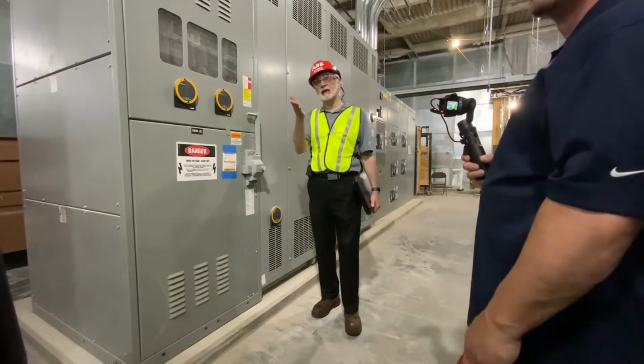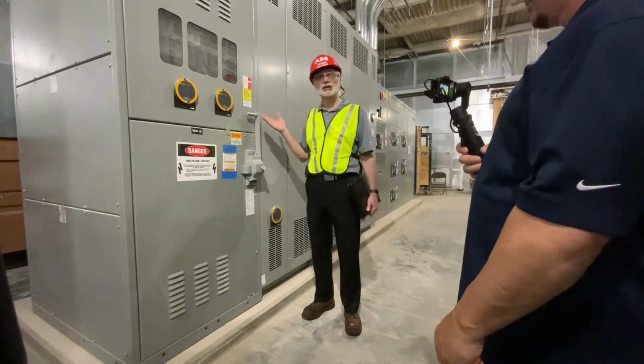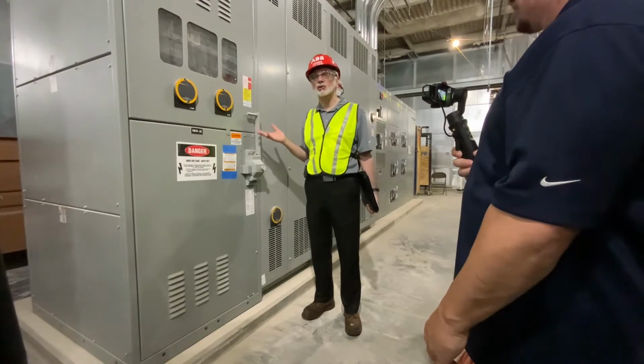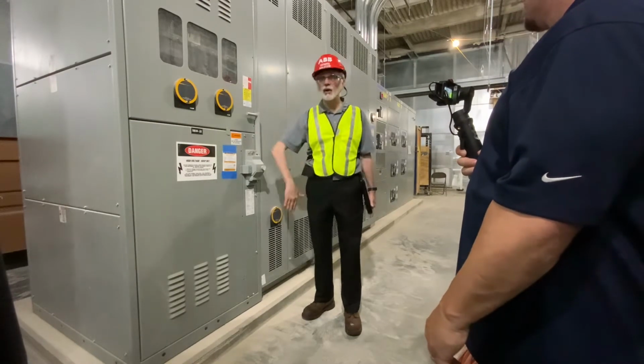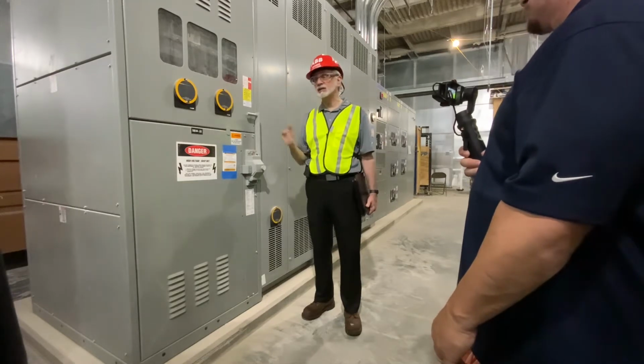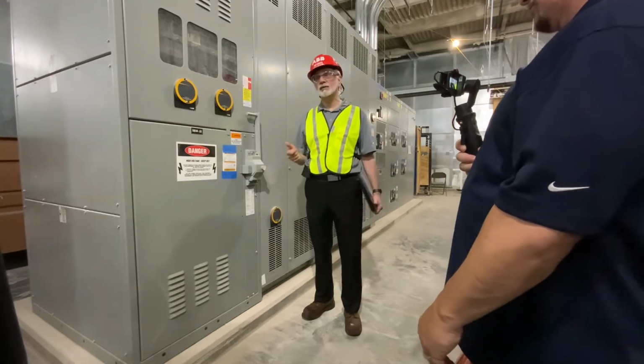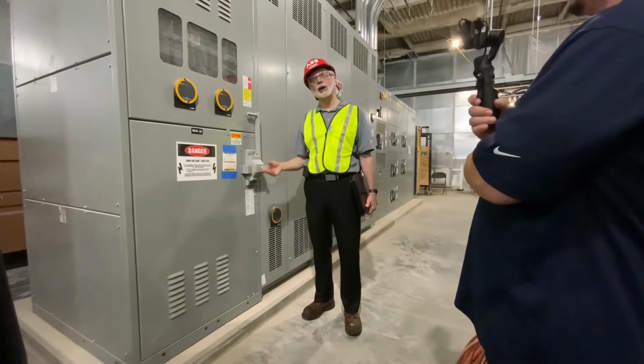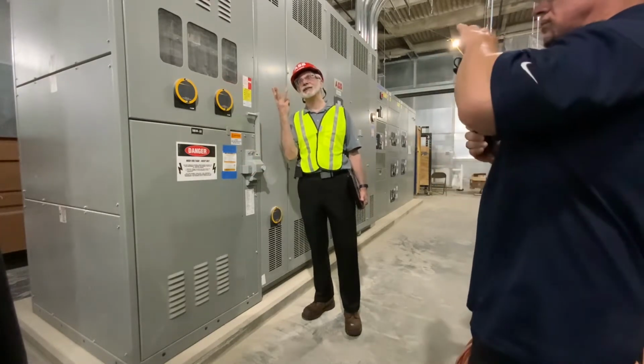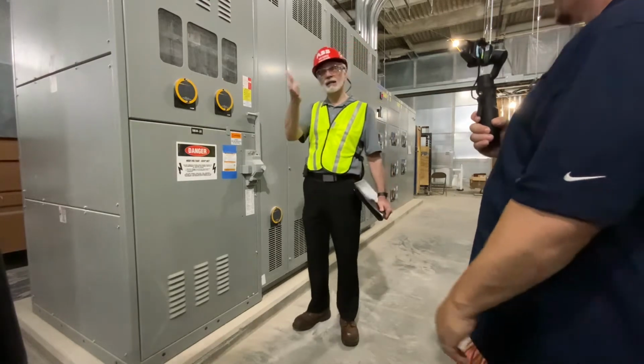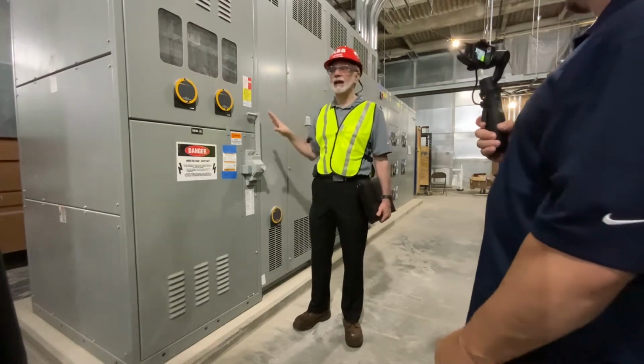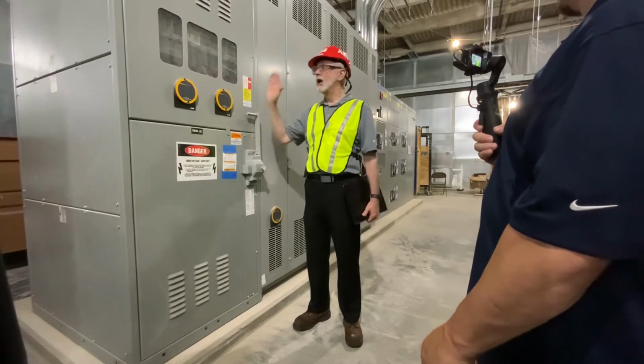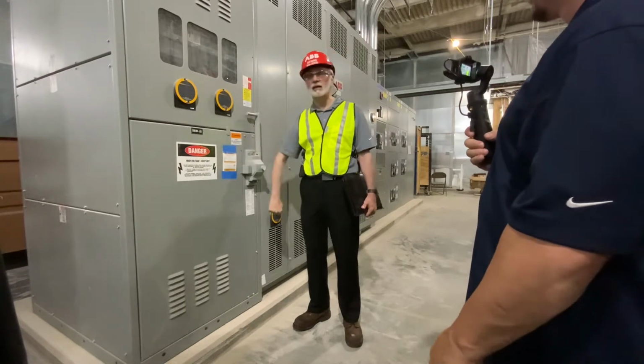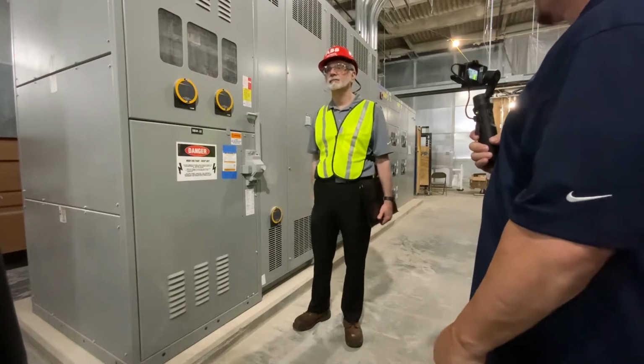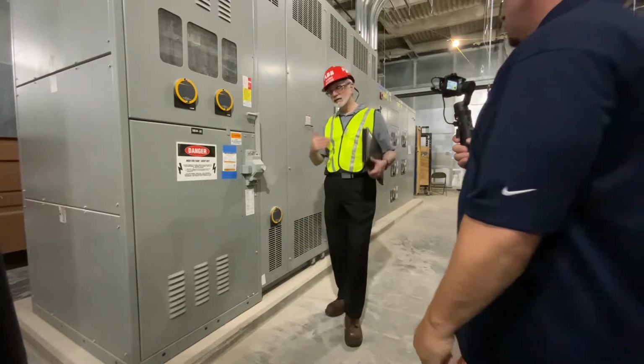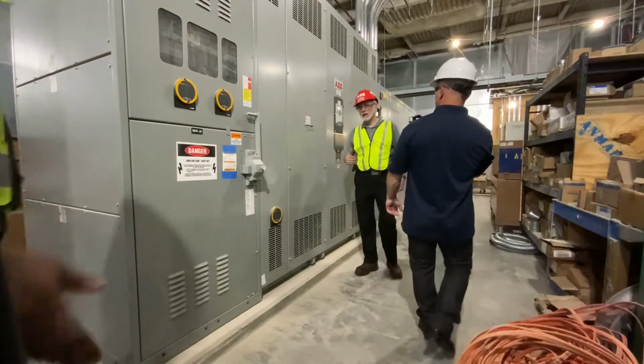The nice thing about this, and that's a great question, is because this is just a switch, there really is no control power requirement. You're either going to throw it on and boom, you got 13.2, or you're going to turn it off and boom, you don't have 13.2, or the fuses are going to blow and boom, you don't have 13.2. Those are really your only three choices. But to your point, you do not have to worry about any kind of control power whatsoever to make this switch operate. It's strictly a manual operating device.